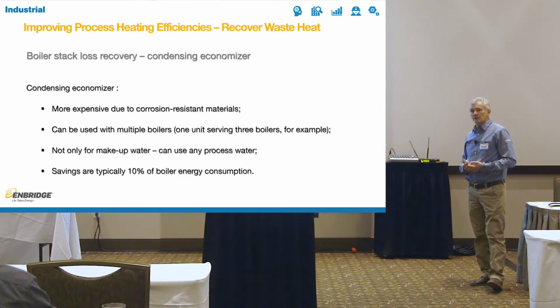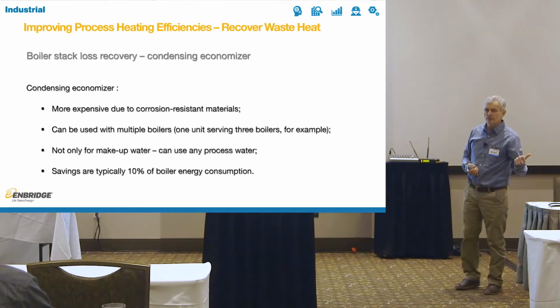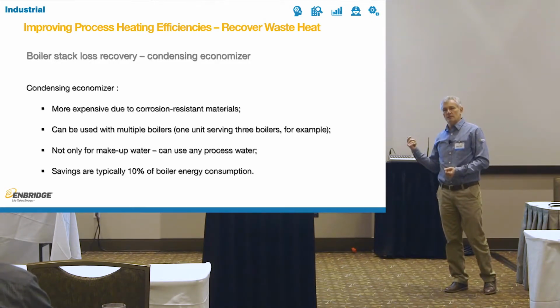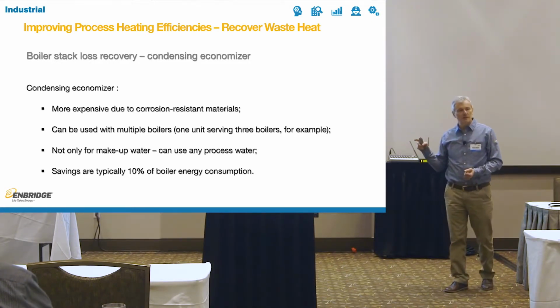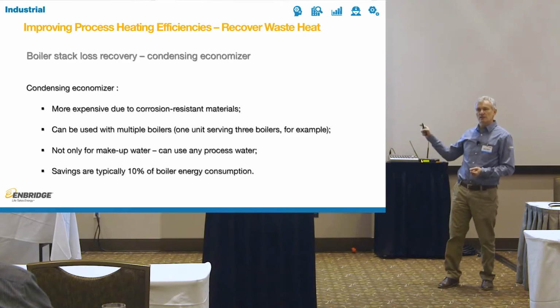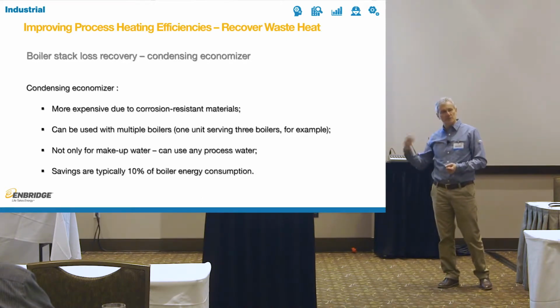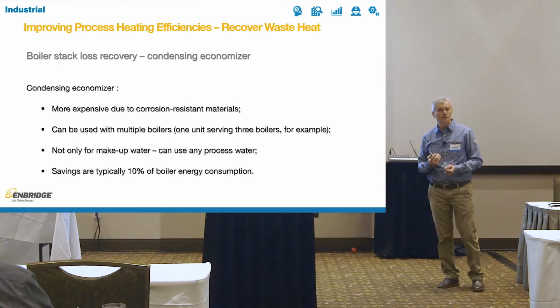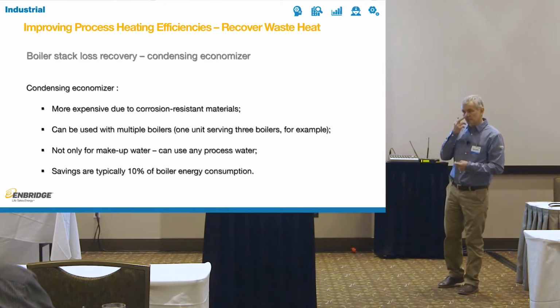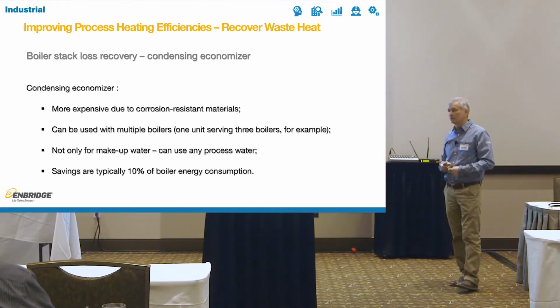Savings are typically 10% in the condensing economizer alone. Remember the Feedwater Economizer, 3 to 5%? This one is 10%. And the way that I implemented it in one case, I actually just had a condensing economizer recovering 14% of the energy all in one. So instead of having 2 different pieces of equipment, I just had one that recovered all of it.